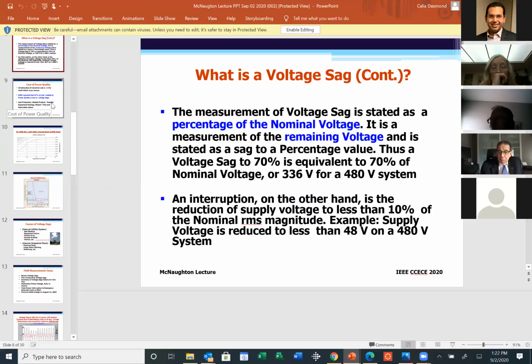The way voltage sags are reported is sometimes as a percentage of the nominal voltage, meaning the value of the remaining voltage, and that's the way IEEE reports it. But based on my field experience, some end users report it as the voltage drop itself rather than the remaining voltage. Regardless, whether it's the remaining voltage or the undervoltage, this is what plants could experience: 30, 40, 50% voltage drops.